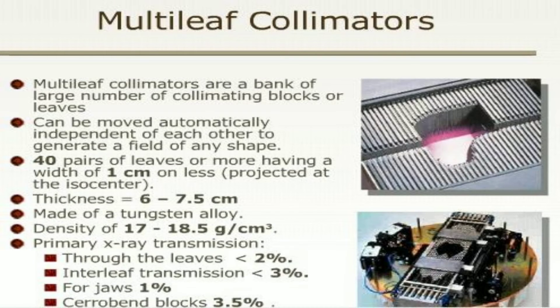Multi-leaf collimators are a bank of a large number of collimating blocks, 40 pairs in number, having a width of less than or equal to 1 cm, with a thickness of 6 to 7.5 cm, made up of tungsten alloy with a density of 17 to 18.5 grams per centimeter cube. Primary transmission of x-ray through the leaves is less than 2%, interleaf transmission less than 3%, for jaw it is 1%, and for Cerrobend blocks it is 3.5%.